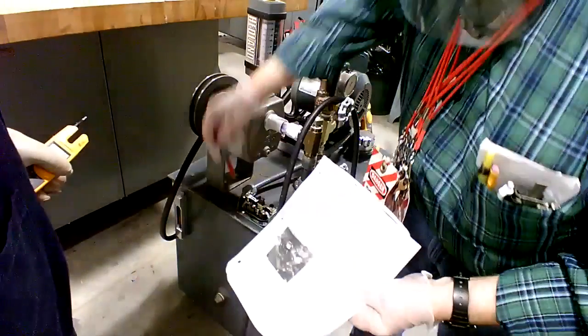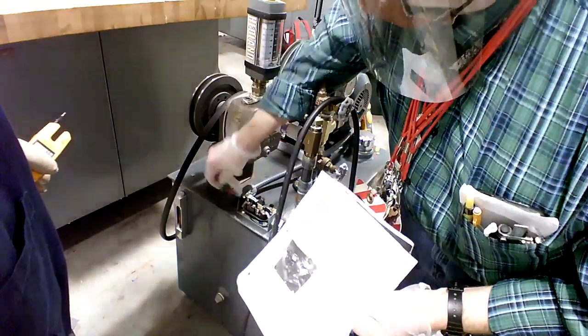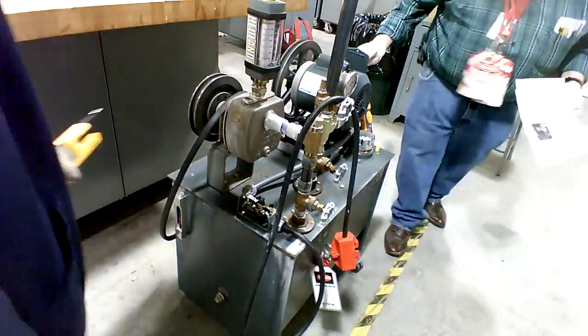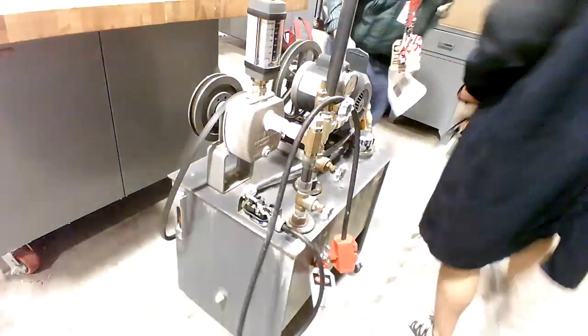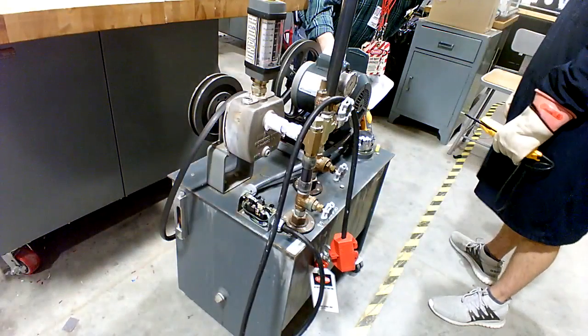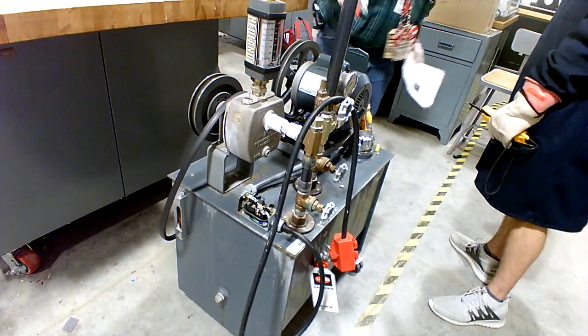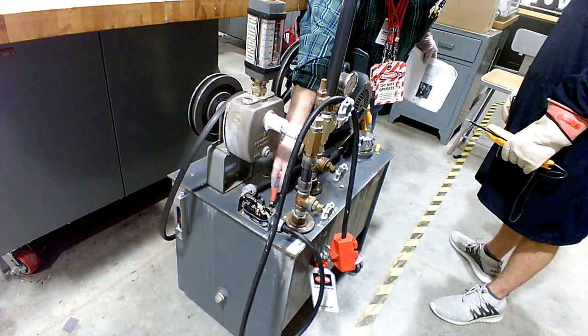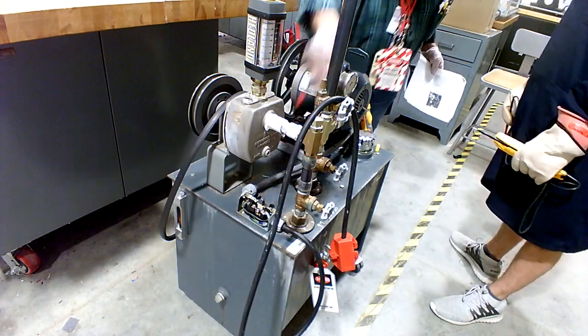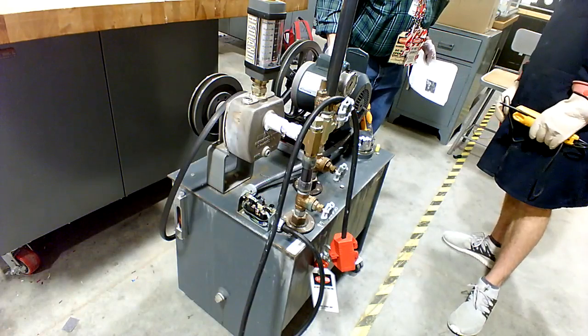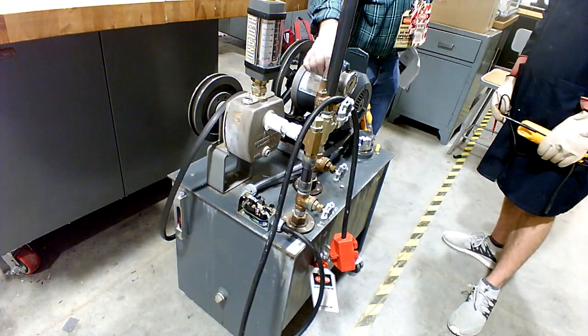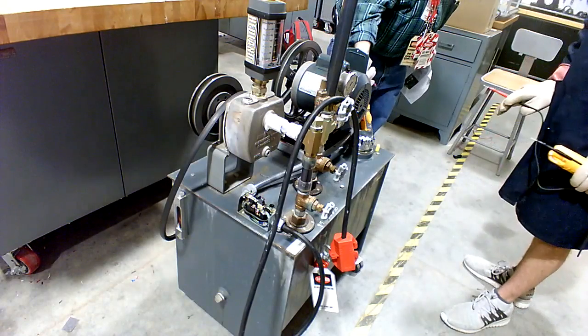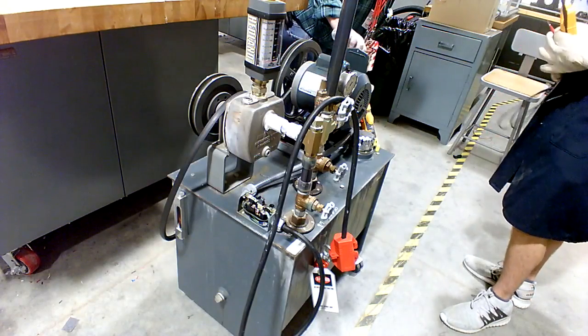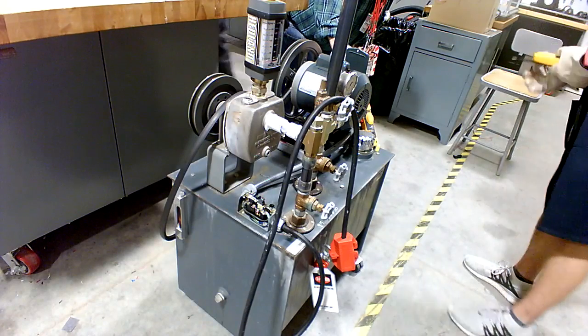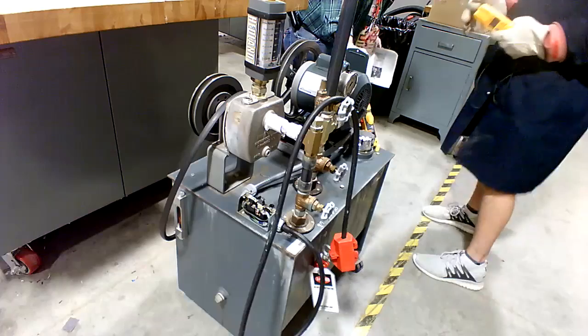It comes in here like this. That's the one that leaves the overload and it goes to the motor. You're leaving the overload here, goes to the conduit. That's the main black wire. That leaves the switch. The neutral, it comes out of here. It's the one that goes straight through. The incoming and the outgoing white wire line up, and it ends up through here. The green one is the one where they plug everything on the screw. It's continuous through here. And it goes through. You see where that ground wire goes to the frame of it? That ground wire is both the middle part.